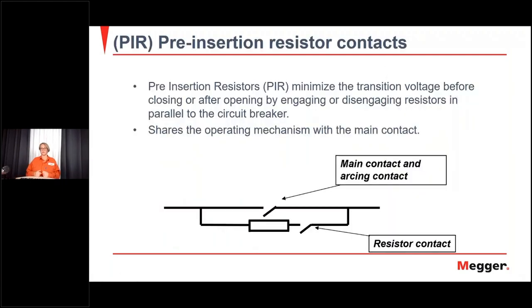Yeah, the pre-insertion contacts I talked about earlier. We want to limit the current and transition voltage when we do closing. And this circuit is connected the whole time when the circuit breaker is closed. So I heard somebody mention one, but you have a resistance in the circuit that will limit the current when it's closed as well. No, if you think about it, you have two parallel paths. So by having this one in parallel, you will actually have less resistance in the circuit. So we don't disconnect this after connection. It will be a parallel path for the circuit breaker's current.